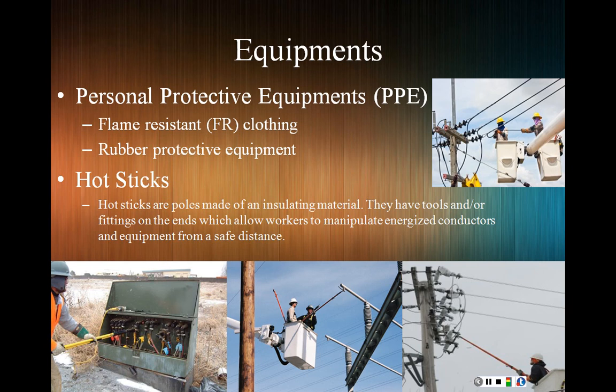As a lineman, we should use rubber protective equipment. Usually linemen use hot sticks to keep the minimum safe distance of 10 feet. Hockey sticks are poles made of an insulating material, because they themselves shouldn't be considered a hazard. They have tools and fittings on the end, which allow workers to manipulate energized conductors and equipment from a safe stand to repair or replace something.